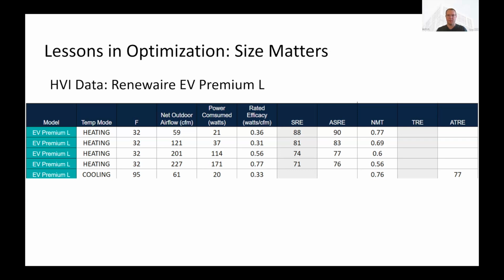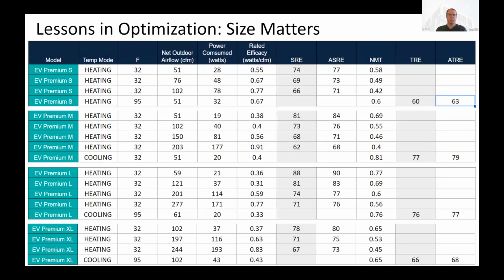Same with this next column over to the right, NMT, net moisture transfer. We have a 77% transfer rate down to 0.69, or 69%. These are really quite big drops, right? Running this system at 60 CFM versus, let's even go to 200 CFM, is a 13% difference in the sensible recovery efficiency, or ASRE. So pretty large differences. We're going to show impacts on buildings in a minute, but I want to point out that sometimes these are not small, right? RenewAire also has not just a Premium L, but an S and an M, and now they have an XL.